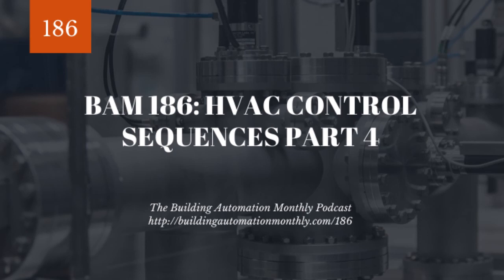But with that being said, so makeup air units, you'll see these a lot in high rises. You'll see these a lot in kitchens. You'll see these a lot in buildings where you're exhausting airflow, and you need to make up airflow into the space. Now, there's kind of 2 ways of makeup air units. You can have makeup air units that precondition air and pipe it into the building, or you can have makeup air units that just supply air into the building or into the airstream. It's kind of 2 different ways.